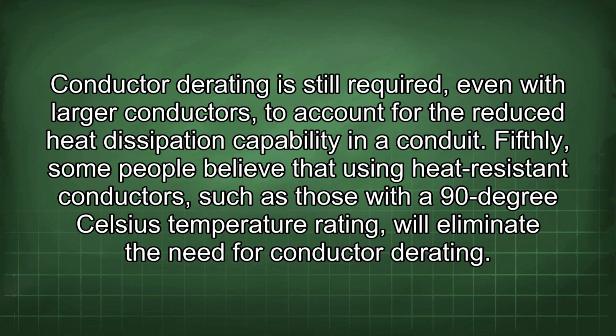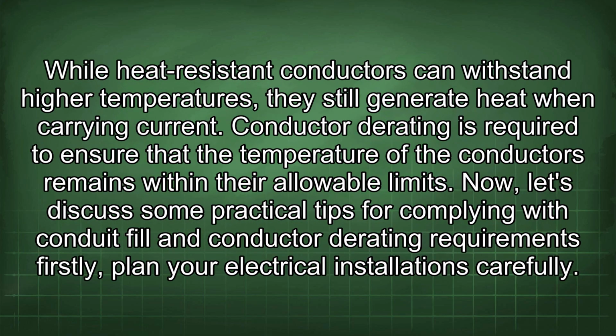Fifthly, some people believe that using heat-resistant conductors, such as those with a 90 degrees Celsius temperature rating, will eliminate the need for conductor derating. While heat-resistant conductors can withstand higher temperatures, they still generate heat when carrying current. Conductor derating is required to ensure that the temperature of the conductors remains within their allowable limits.